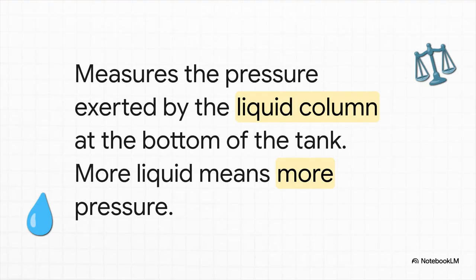First up, we've got the real workhorse of the fleet: the hydrostatic sensor. The principle here is beautifully simple. The deeper the liquid, the heavier that column of fluid is, and so the greater the pressure at the bottom. By putting a sensor right at the bottom of the tank and measuring that pressure, you know exactly how much liquid is sitting on top of it.